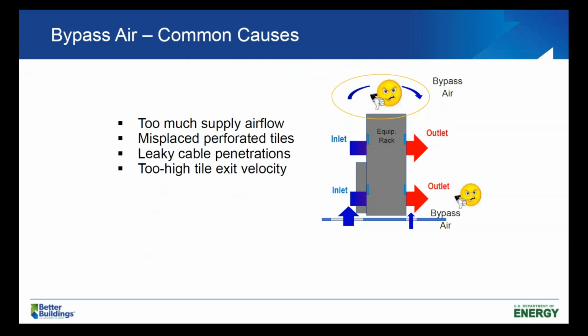All right, so bypass air, again, it's common in pretty much any air-cooled data center. If you have more supply airflow than you need, you'll tend to get more bypass. Misplaced perforated tiles, like as shown there on the right, a perforated tile in the hot aisle, that will result in bypass. Cable penetrations are a common source, and airflow velocity that's too high coming out of the floor tiles. Next slide.